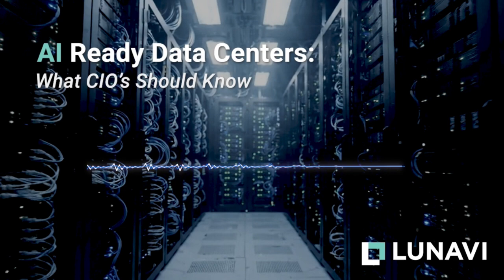I'm looking at a glaring mathematical problem here though. We established that the incoming wave of top-tier AI training hardware pushes 120 to 140 kilowatts per rack. If rear-door heat exchangers cap out their efficiency at around 60 kilowatts, this bridge falls woefully short. A CIO running elite training models is going to melt an RDHX setup. You're not wrong. The physics of air exhaustion eventually loses to the density of the silicon, no matter how good your radiator is.